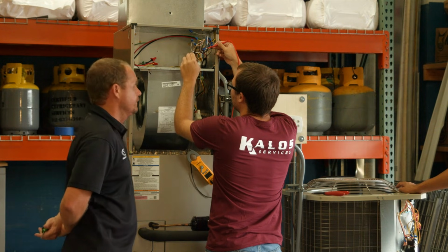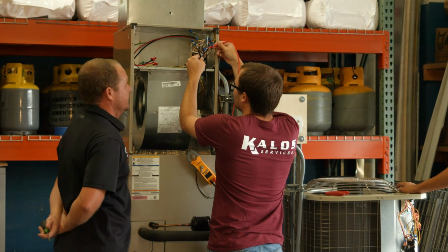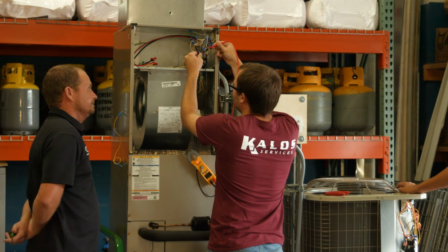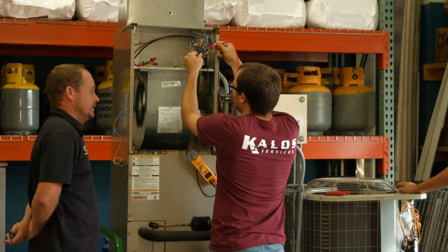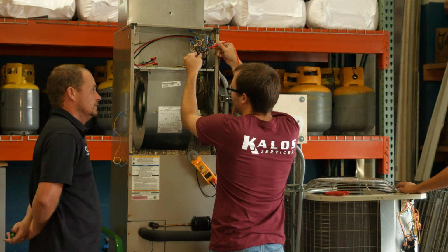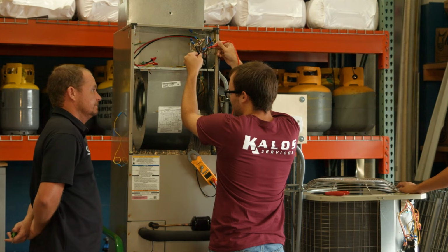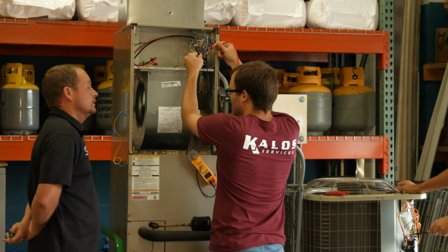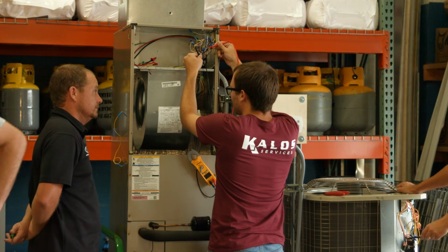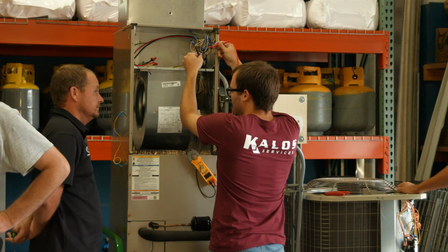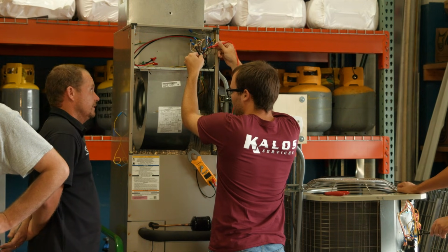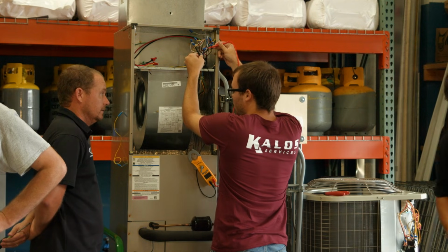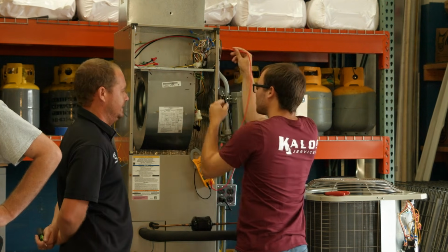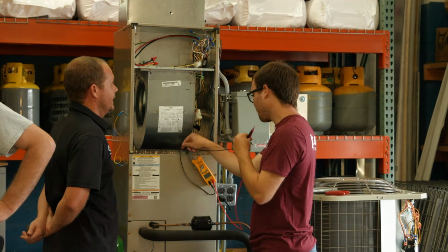You're getting 27 volts at the connection in the air handler. Correct, between your thermostat and your air handler. So at that point it would be between the air handler and the condenser? Between the thermostat wire coming out of the air handler to the condenser, there is a what in that wire? There's an open. An open in that wire, exactly. That's what I was looking for. Okay, so that is what you want.